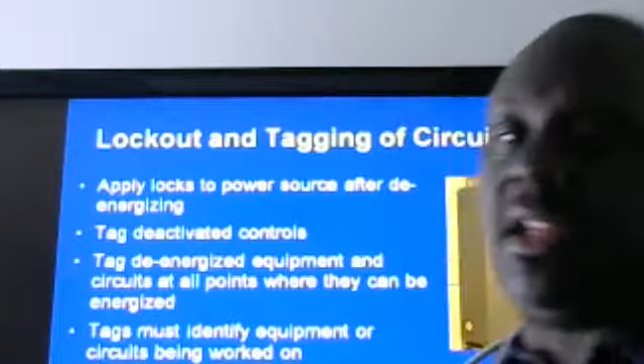Somebody is changing the motor on a conveyor belt, for instance, and they turn the electric off. So what we'll do is just put a tag on there, Earl's shift is 7 to 3, motor change, and then lock that out. Because at lunchtime, I could go to lunch, and somebody could come in and say, why is the belt off, and hit the switch back on. I come back from lunch, touch the wires, they're now live, and the shock runs through the whole body, and death could occur in minutes. So the lockout tag out scenario works very well there.